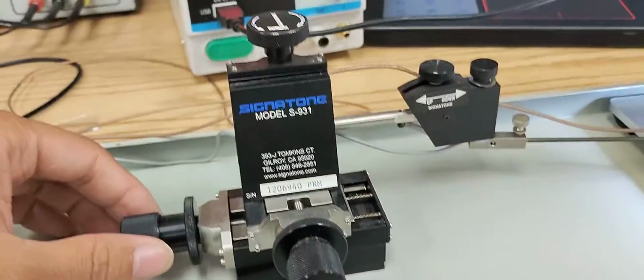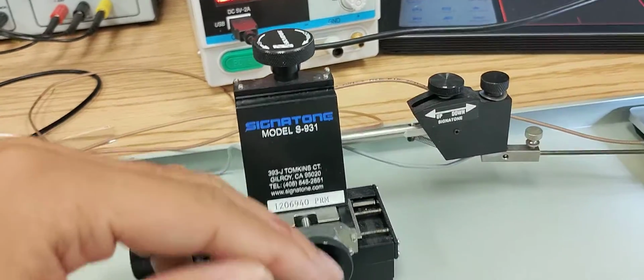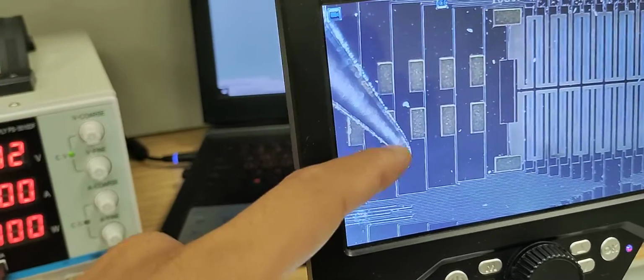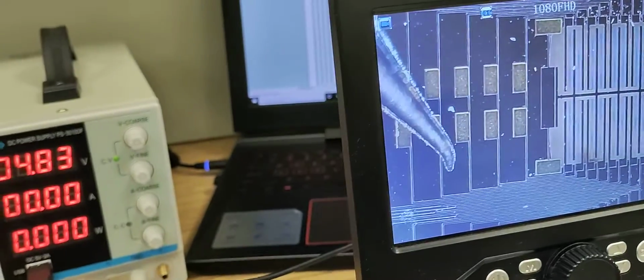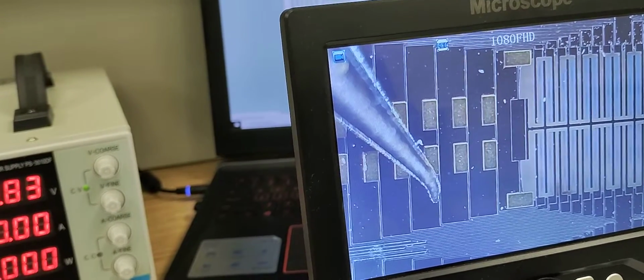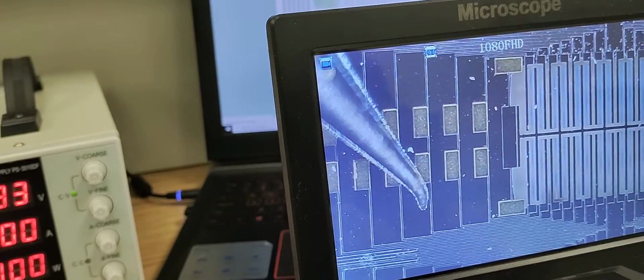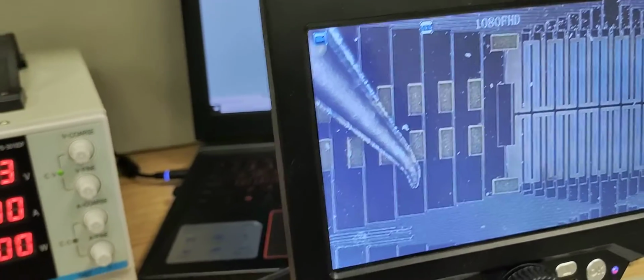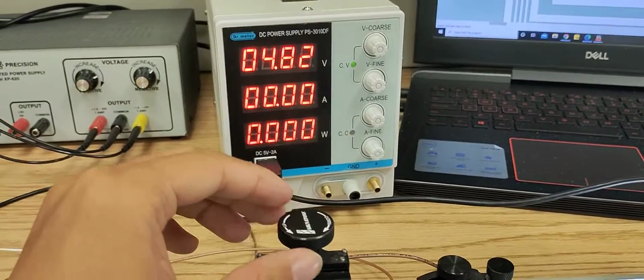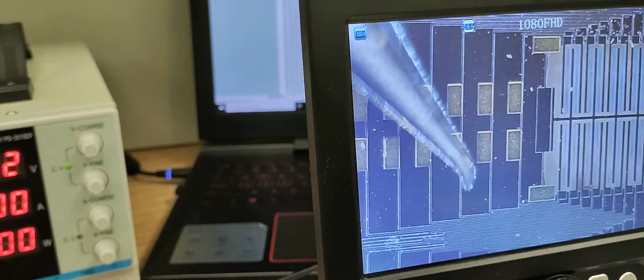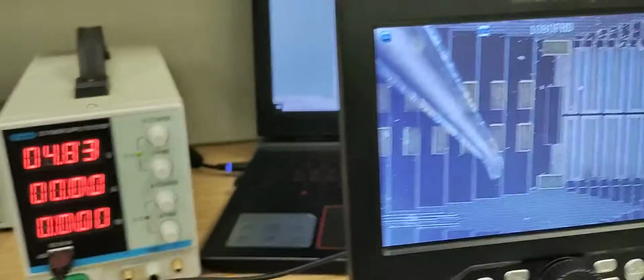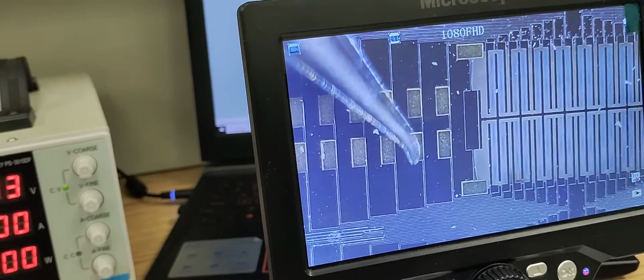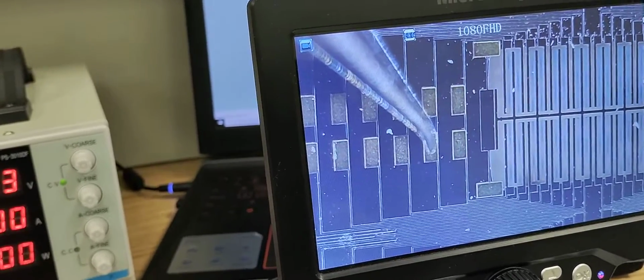And then you can use the backward and forward button and the left and right side button to position the tip to the pad where you want to probe. So I'm going to move that forward. See, so now the probe is getting too close to the device. I'm going to lift it by a little bit. Okay, so continue to move that forward, and also use the left and right side button to move the tip of the probe to the position you want to probe.